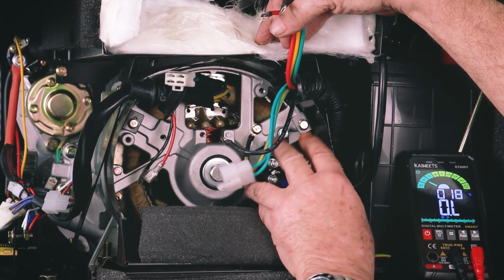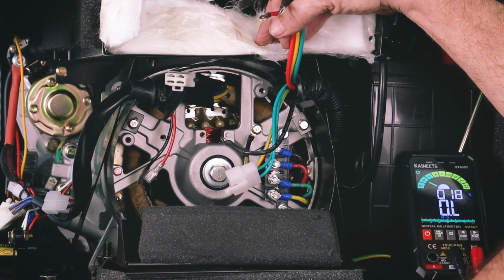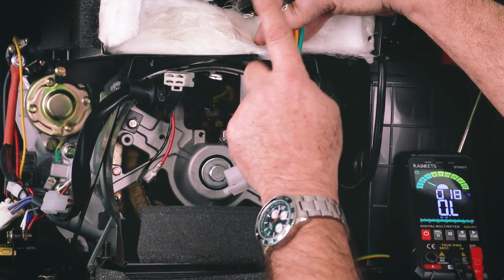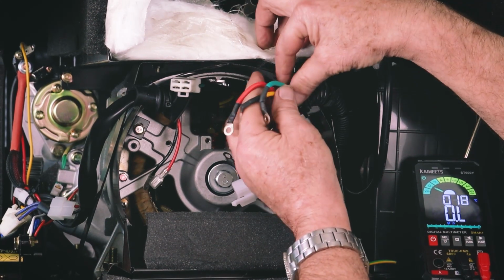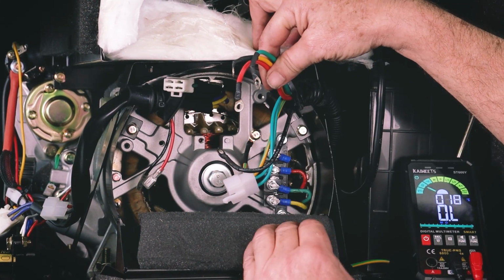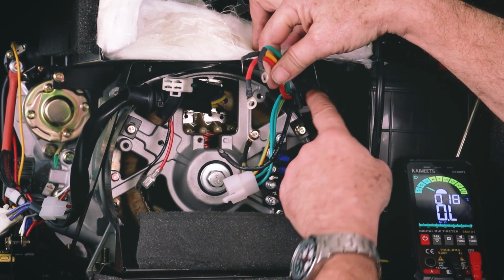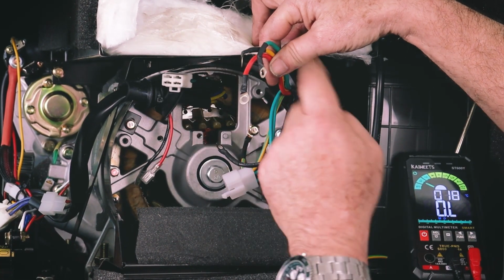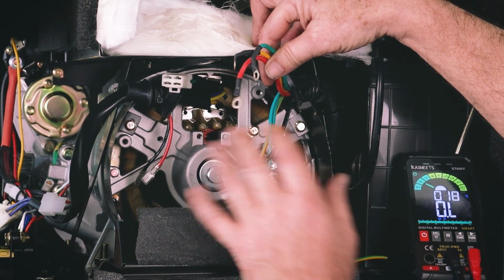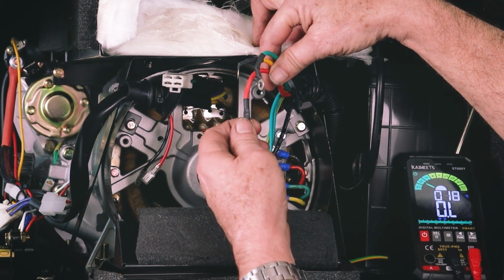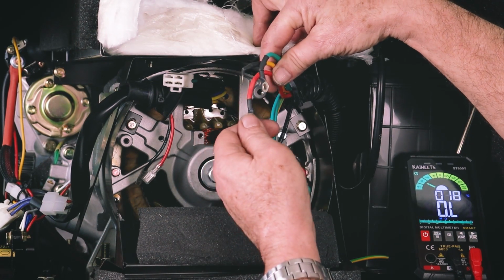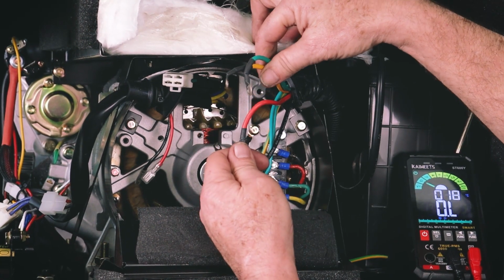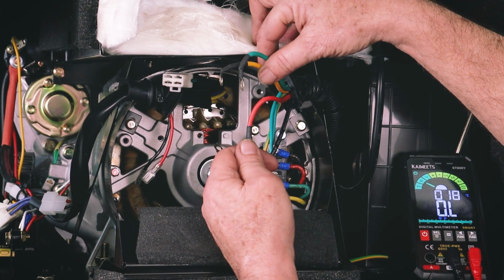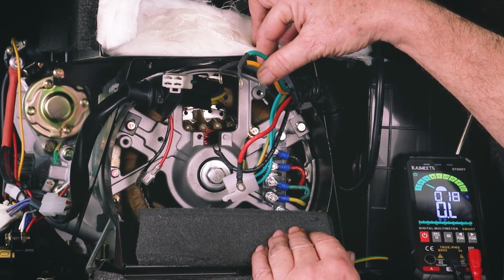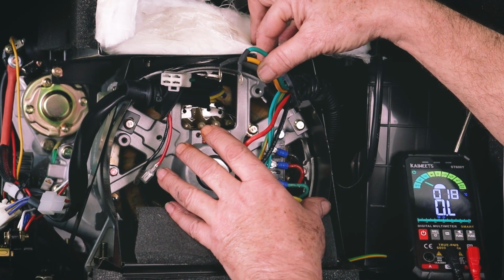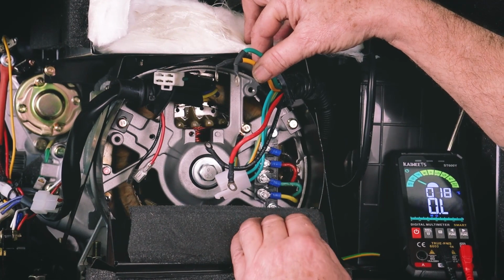If we're getting it down there, and we're not getting it up at the control panel, this is another scenario, then we would suspect a break in these 4 wires somewhere between here and the control panel. That can be easy to rectify. We basically just replace the 4 wires that run from the alternator up to the back of the control panel, and that will probably fix our problem. But you can always put a test meter this end and the other end to make sure you're getting continuity again, the beep test. Red wire this end, red wire to the other end. Let's see if we've got continuity between here and the control panel, because it may be that the alternator's putting out voltage as it should, it's just not getting up to the top.